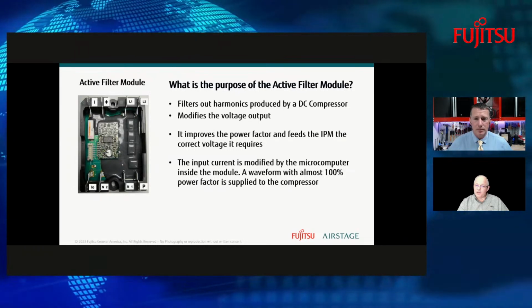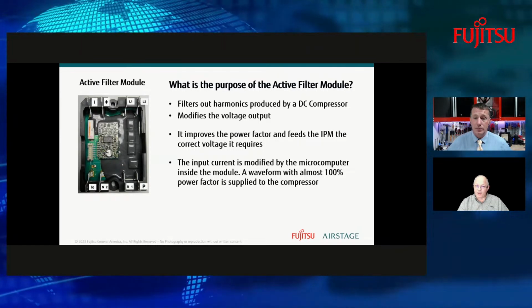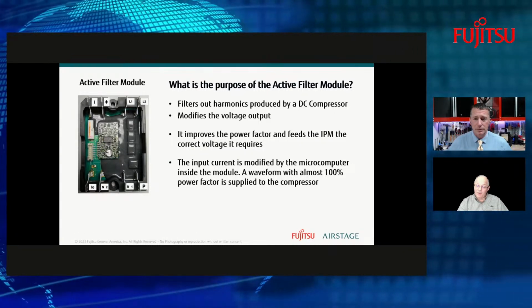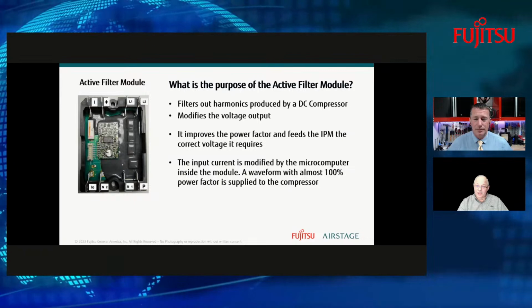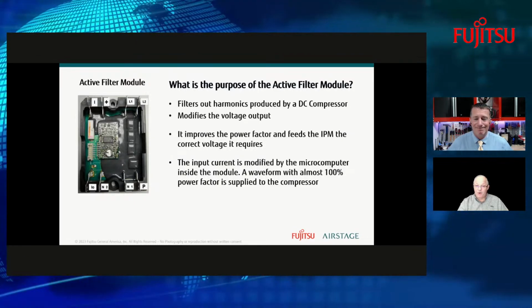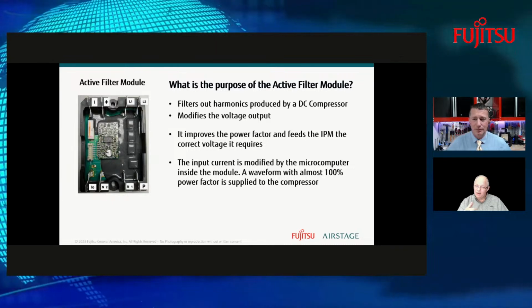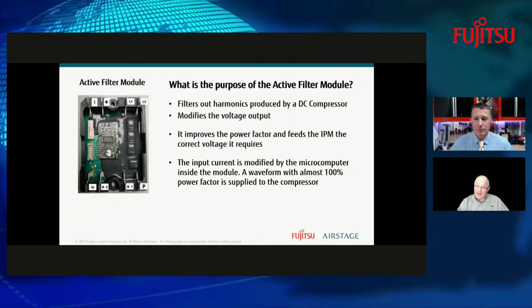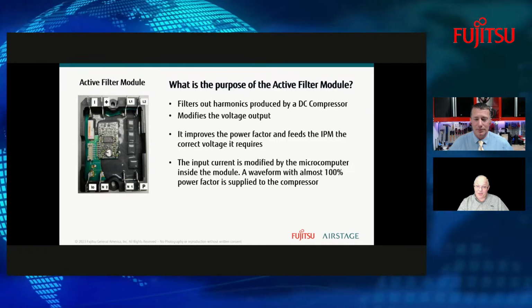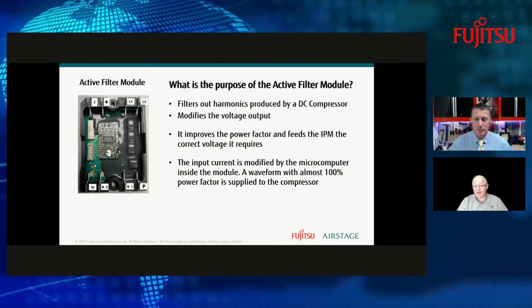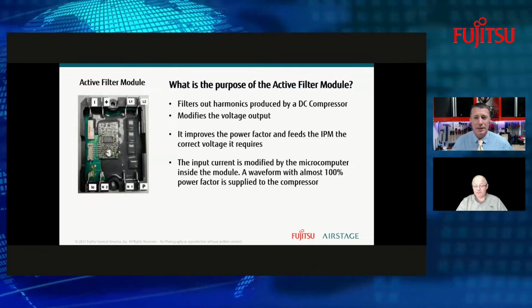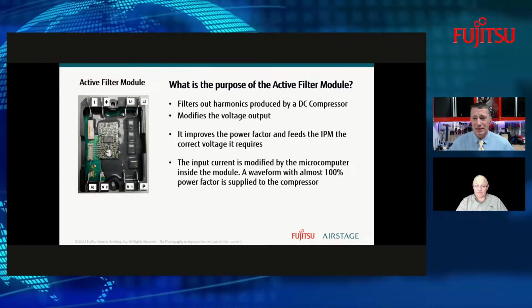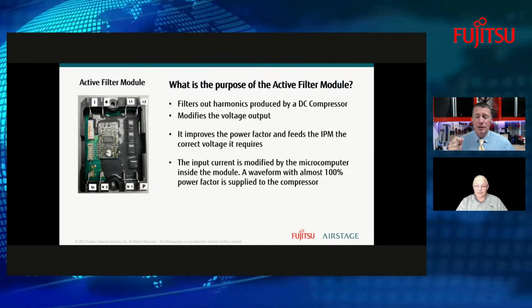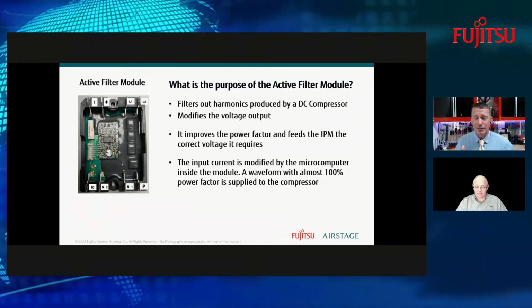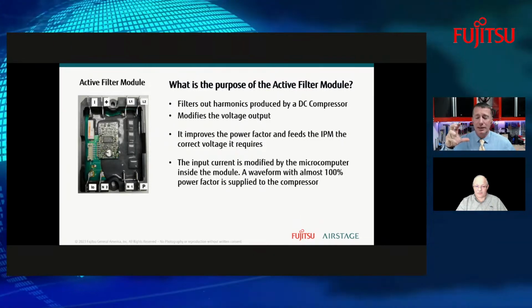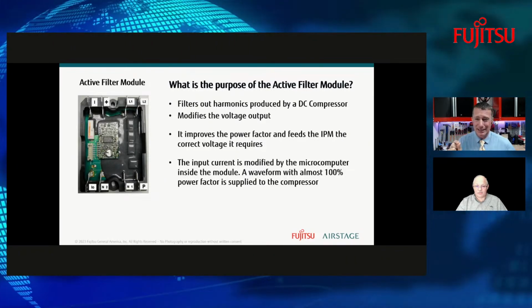Well, a lot of times technicians don't check the incoming voltage to the equipment. Oh, okay. Sure. So if the power company is giving you higher voltage than the system is supposed to have, it could take out components like this because it's generating more heat within the module itself. So they don't know that that's what's causing it, but that is a very high possibility that you could be getting some higher voltage. Now, when I was out doing education at the distributor level, I always encouraged voltage monitoring devices for my inverters, like the ICM, like the 493s, and units that actually help modulate the incoming voltage.